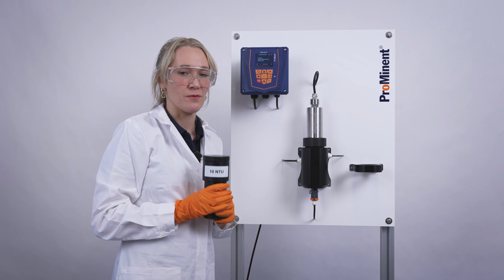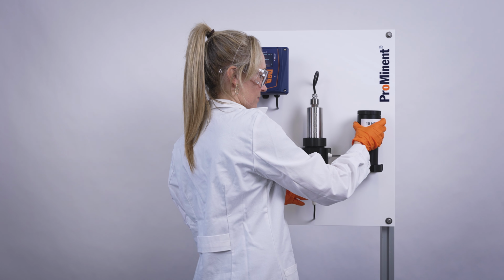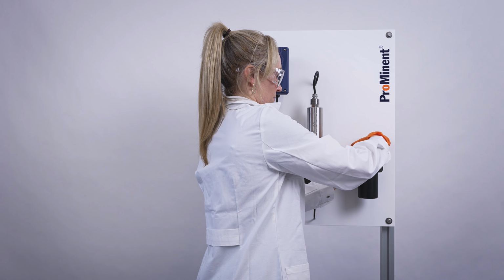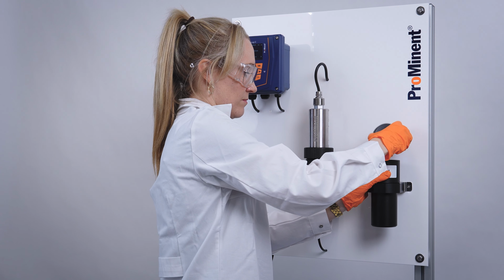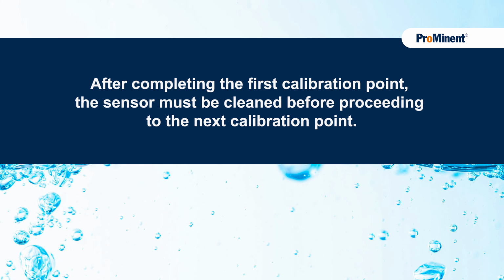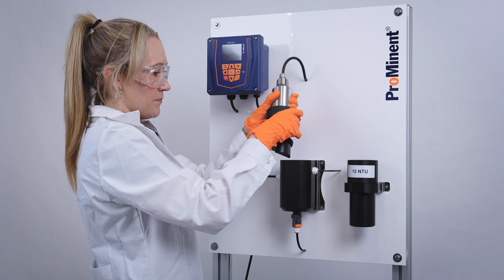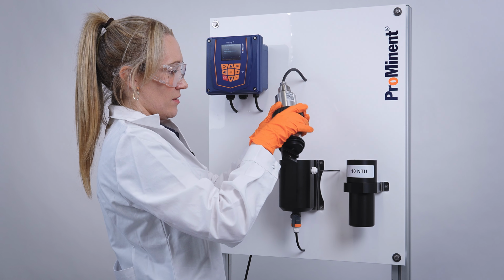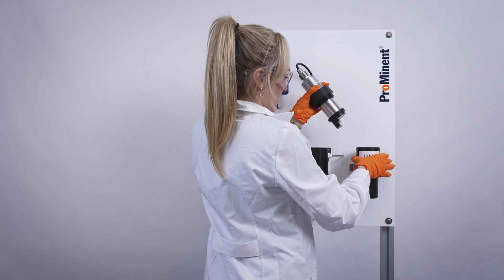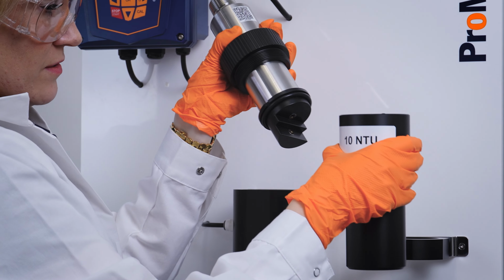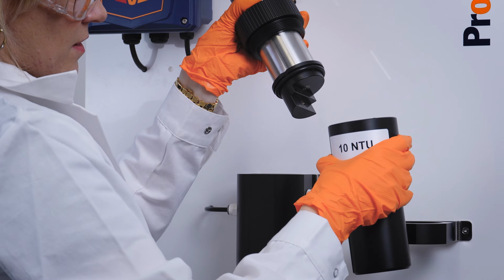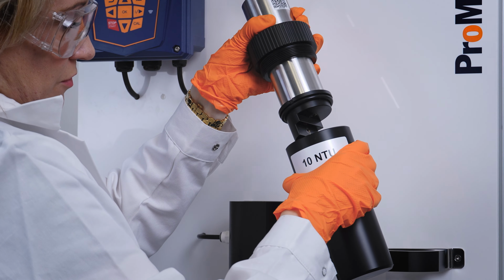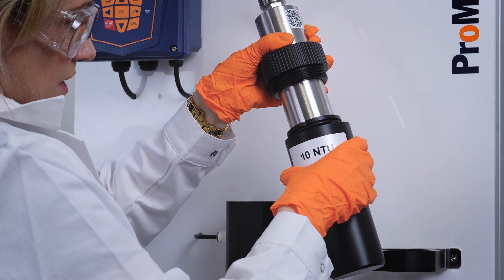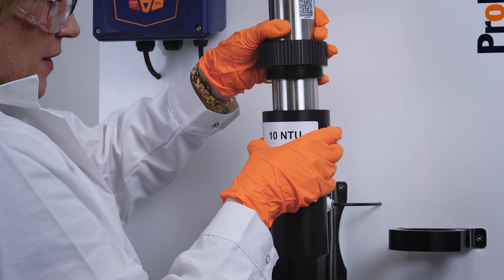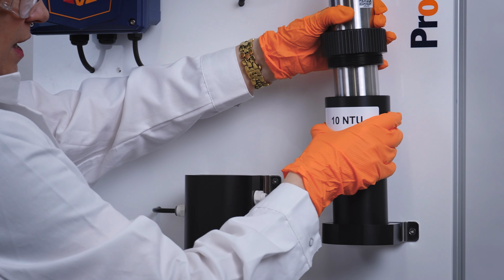Now you repeat the same process with a 10 NTU standard. Again, take the sensor, clean it, I just did it, turn it, take the calibration vessel, both of them at 45 degrees, and insert the sensor into the calibration vessel. Then put it into a vertical position and back to the holder.